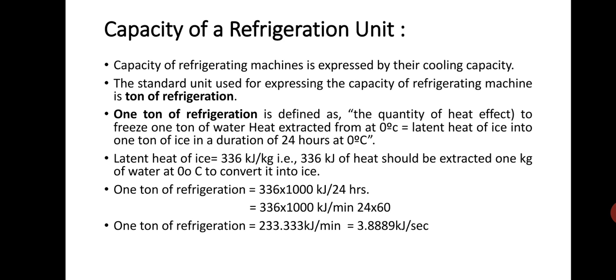So this is the numerical value for 1 ton of refrigeration, that's equal to 336 into 1000. 1000 is the density of water, kilojoules per 24 hours. So 336 into 1000 kilojoules is converted into minutes, 24 into 60. Next we convert into seconds. 1 ton of refrigeration is equal to 233.333 kilojoules per minute. That again is converted into seconds, 3.8889 kilojoules per second. So this is the final value of the 1 ton of refrigeration unit.